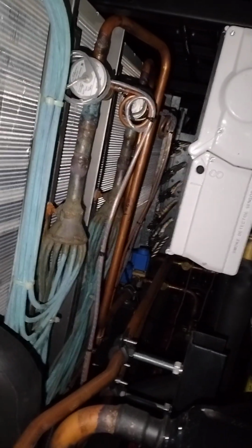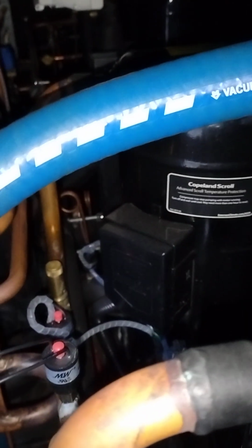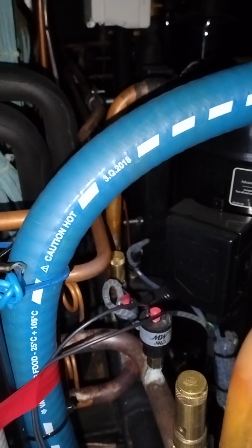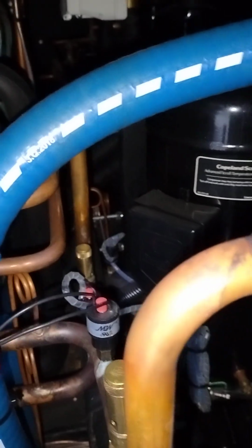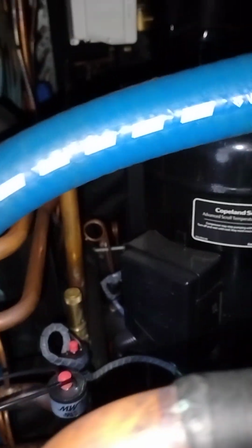And all this enclosure is actually a part of the air path. One of the normal good designs for these units is that the compressors can be in a separate compartment, almost like it is here. However, they need to be maintained without having the air path closed or shut off, so it can be separate. But in this design, it's a little bit hectic, to be honest.